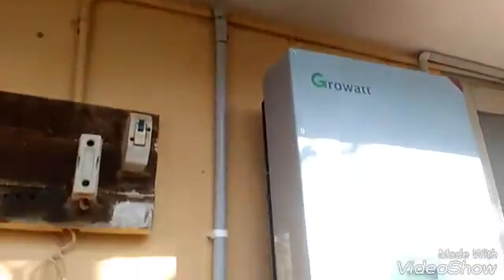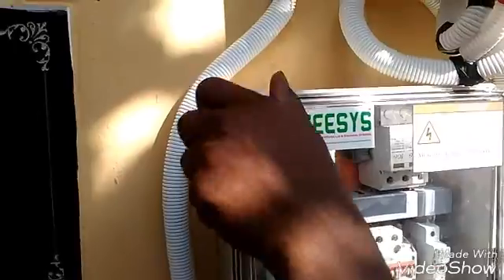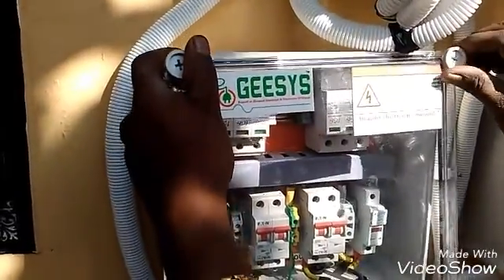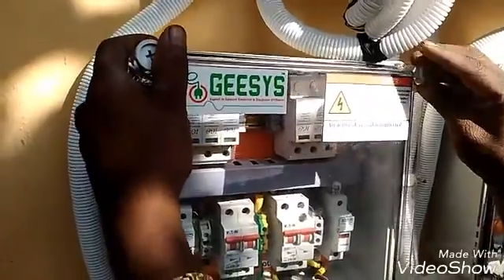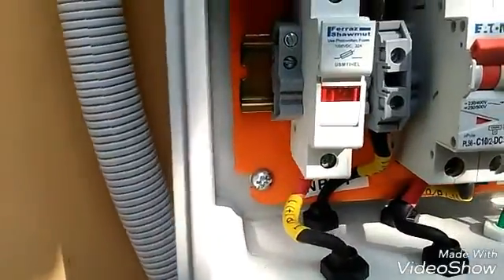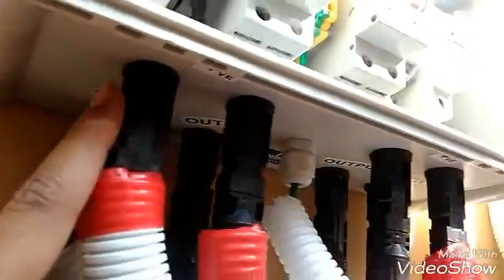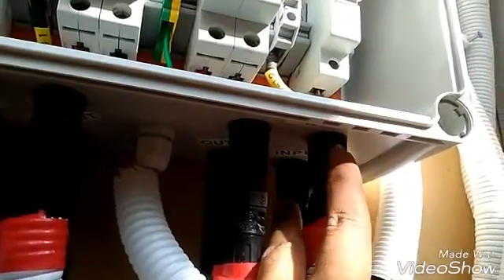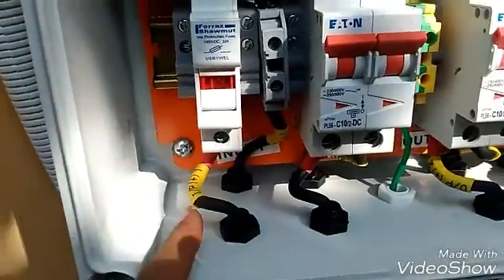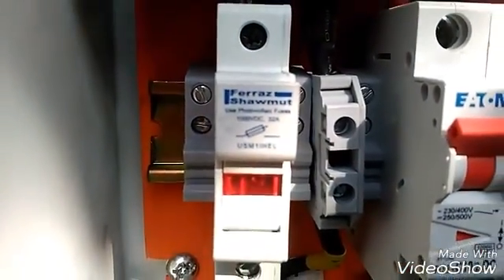From here the wire comes towards the inverter. This is a Growatt 5 kilowatt inverter. This is a DC box — the four wires come into this DC box, which has two inputs and two outputs, working as an isolator between the PV and the inverter. There are two input wires for each array, and after the input there is a 1000 volt, 32 amp DC fuse to protect the inverter system in case of a short circuit.